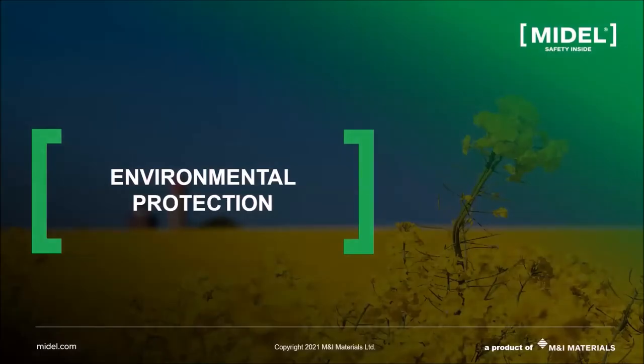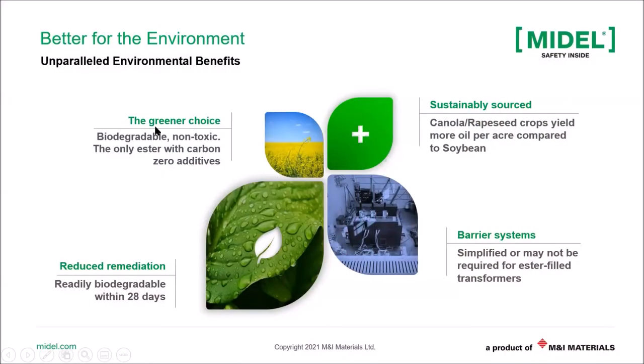So the other benefit I want to highlight is environmental protection. MIDEL ester liquids are considered biodegradable and non-toxic. They are the only esters with carbon zero additives. Our canola and soybean are sustainably sourced. In fact, the canola crop yield is twice as much as soybean, so there can be more canola oil produced from the same amount of land, twice as much as soybean. And the barrier system can be simplified because of several factors, one of them being that when you have the fire suppression system removed over a transformer, and the transformers are closely located to each other, you can simplify the containment and bring it closer.